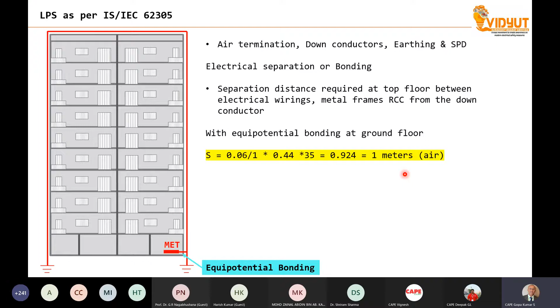you have the building here, and this red color is the air terminal, air termination and down conductor, and the S stands for the separation distance. In order to avoid spark over or flash over between different objects, down conductors shall be at least, for example, 1 meter away from the frame of the structural steel, electrical wiring, rebar, metal doors, metal windows, and so on.